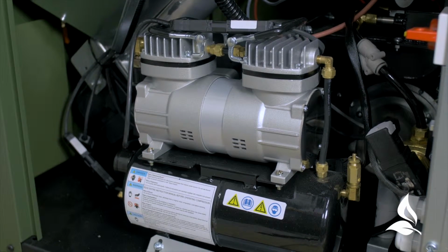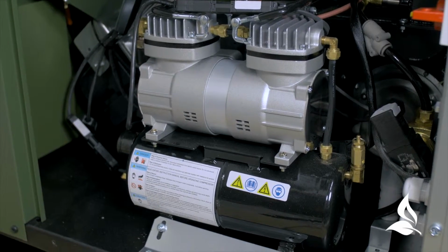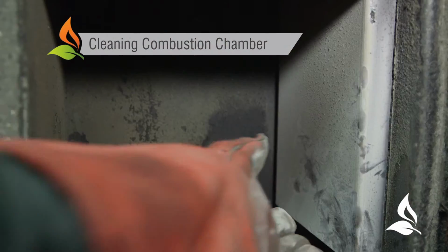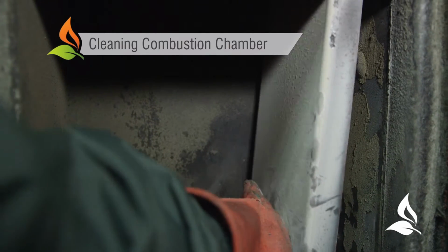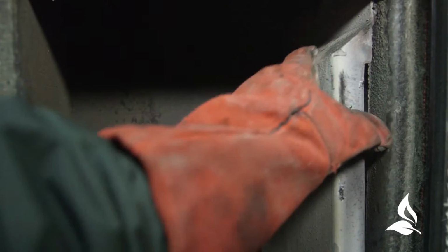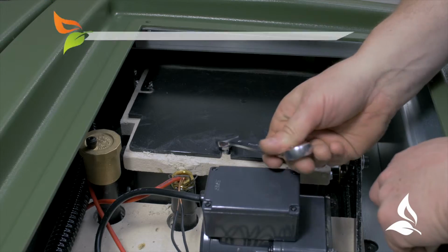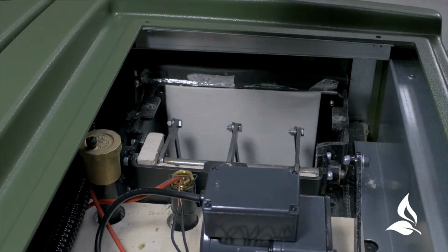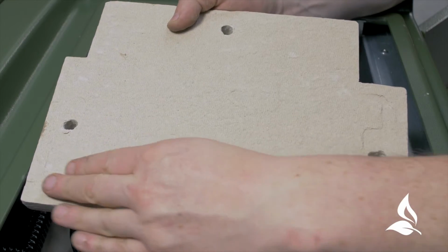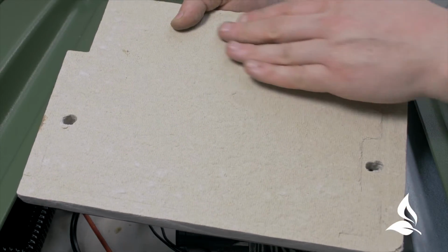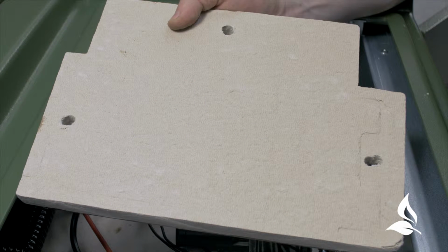Let's go through each of the tasks that need to be undertaken as part of a service call. Cleaning the combustion chamber. Remove the baffles from the main combustion chamber and clean down all heat exchanger surfaces. Remove the turbulator cleaning mechanism from the boiler and clean the heat exchanger tubes. When removing the turbulators from the heat exchanger, check if the fibre board needs replacing. Service engineers often omit to replace this board, and it leads to poor quality combustion by air getting sucked in if it is not a tight seal.